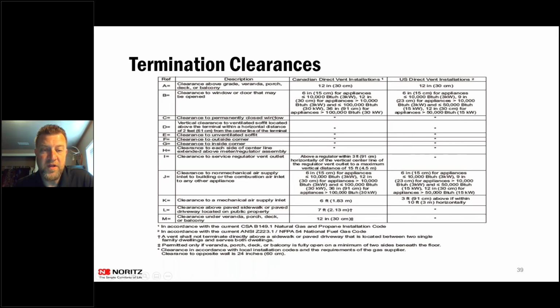Clearance to a permanently closed window, so next to a window that cannot be opened, there is no clearance, but there is a little asterisk here. If you look down here at the bottom, that asterisk is saying that we don't require a clearance, but local codes may be different. So if it doesn't specify here, you do have to go off the local code. If your local code says you still have to be 12 inches away or whatever, you still have to abide by that. Typically, with a permanently closed window or something like that, it doesn't make a difference. They don't require that.